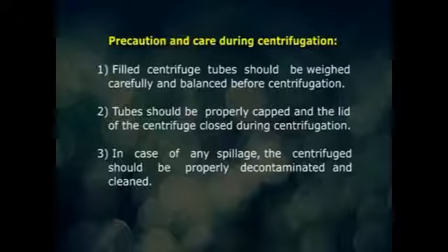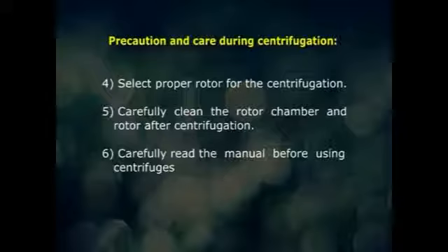Certain precautions and care should be taken during centrifugation. A few of them are: the filled centrifuge tubes should be weighed carefully and balanced before centrifugation. Tubes should be properly capped and the lid of the centrifuge should be closed during centrifugation. In case of any spillage, the centrifuge should be properly decontaminated and cleaned. Select the proper rotor for the centrifugation. Carefully clean the rotor chamber and the rotor after centrifugation. Carefully read the manual before using centrifuges.